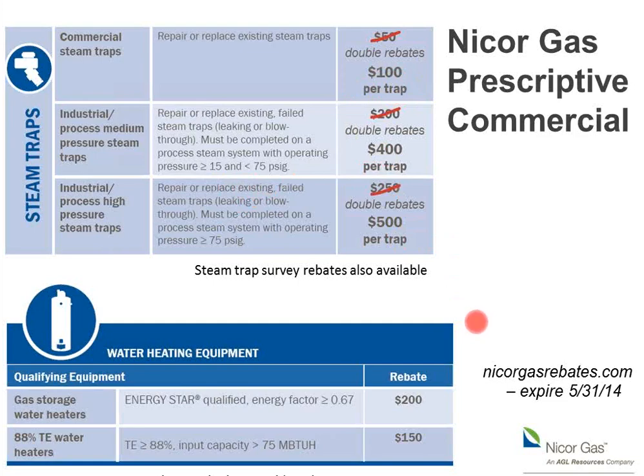There's also a program where they will pay you a rebate to do a survey of the steam traps, and then if you fix a certain percentage of them, you get the rebates for the traps, and you also get the rebates for doing the survey on all the traps. So you go in and do a survey on 100 of them and document it, but you only have to fix 30 of them or something.